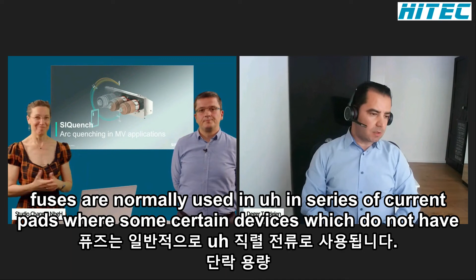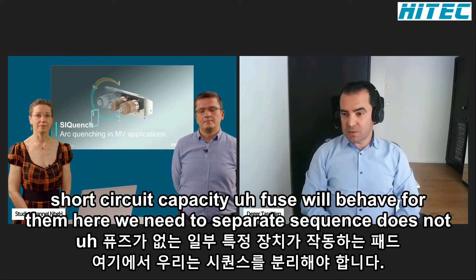So, is there any interference in the use of SIQuench and limiting fuses? Here, maybe we need to make a separation. Fuses are normally used in series of a current path where certain devices which do not have short circuit capacity - the fuse will behave for them. Here we need to separate: SIQuench does not make a breaking function. SIQuench, just the opposite, it makes an earthing, or it makes a closing onto, let's say, earthing. Therefore, these are two different issues, and fuses are not to be used on the path of a SIQuench, because otherwise, in case of a short circuit, it may melt and really block the usage of SIQuench. Two different procedures, two different working philosophies.